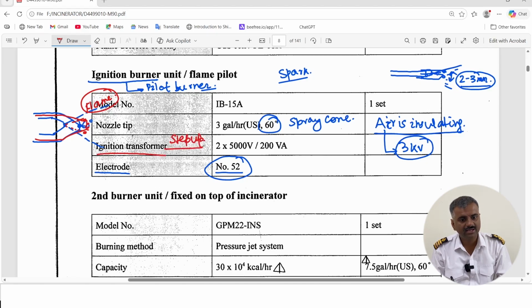Since we know that our vessel is producing 440 volts, you need to step this up to at least 2 into 5000. That means there are 2 electrodes, each having a 5000 volt supply, so a total of 10,000 volts is generated over here. Okay, 2 into 5000. This is the power rating for the ignition transformer, 200 VA.